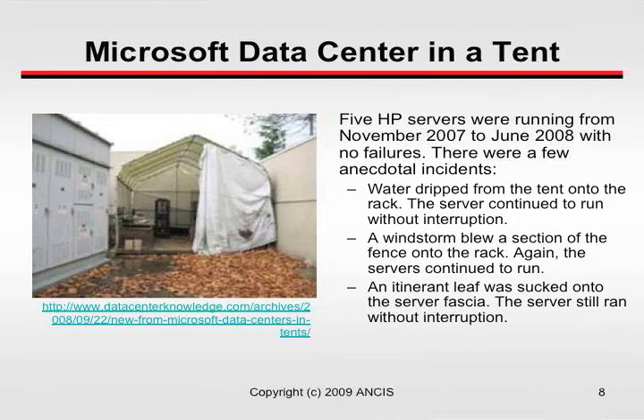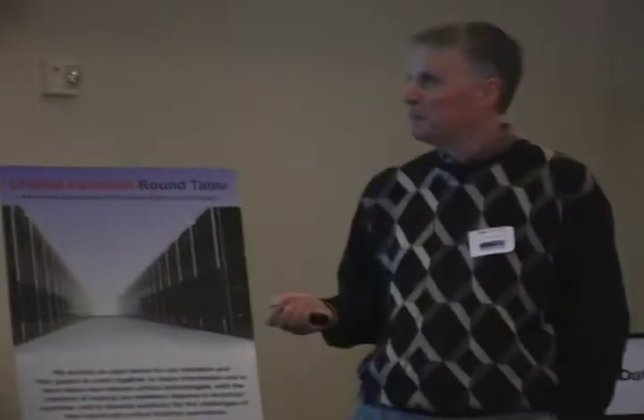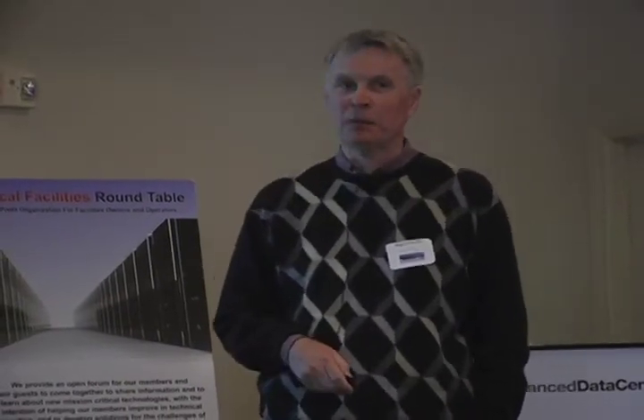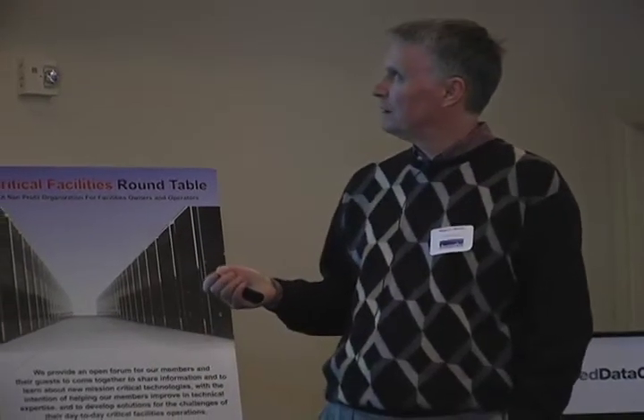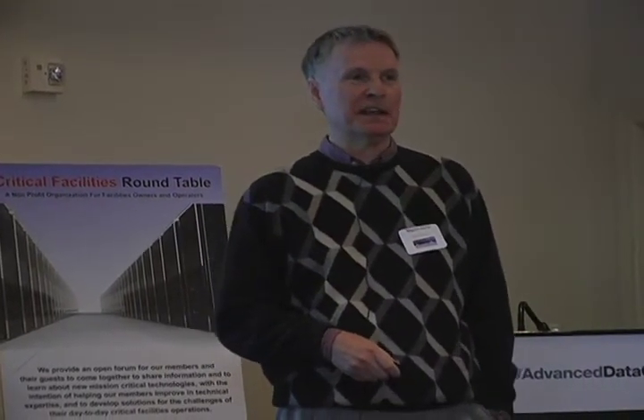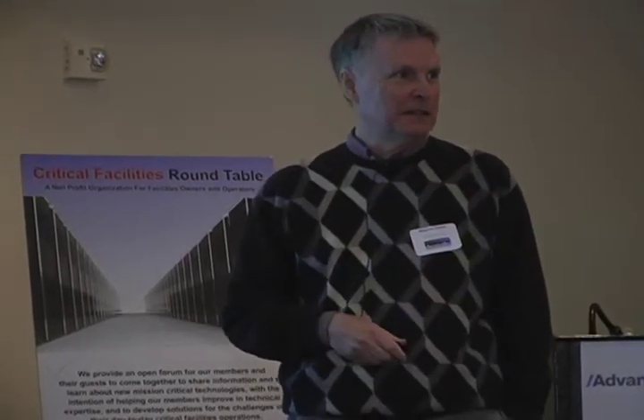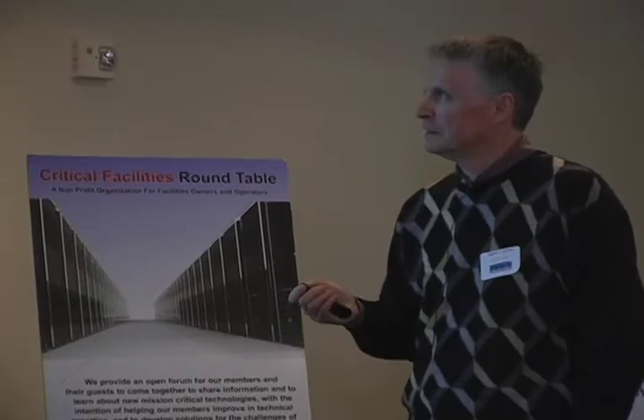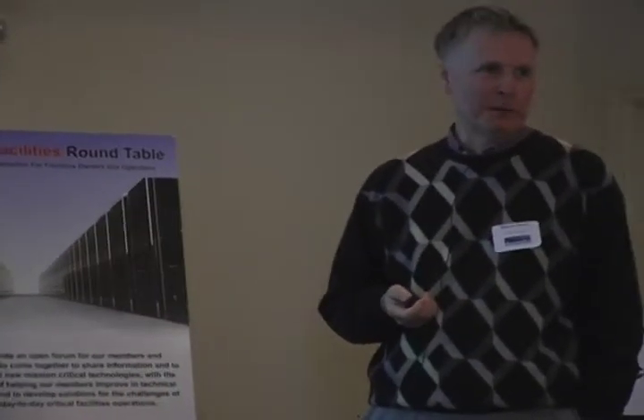So Microsoft, for example, they have really questioned these new recommendations and more or less pulled out from participating in the work at ASHRAE. So they want to demonstrate that servers are very robust pieces of equipment. So behind their building here, they put up this tent, they put in 5 HP servers, and they let them run for a year, and it was raining, and leaves were flying around, and no temperature control at all, no humidity control, there was no control. And it turned out that they just continued to run there, there was no problems.